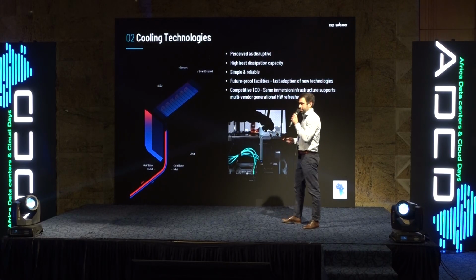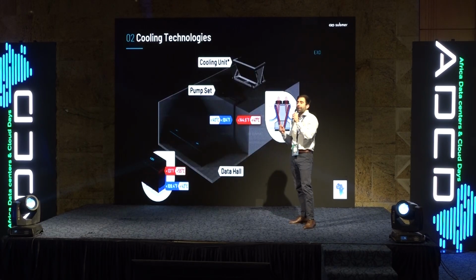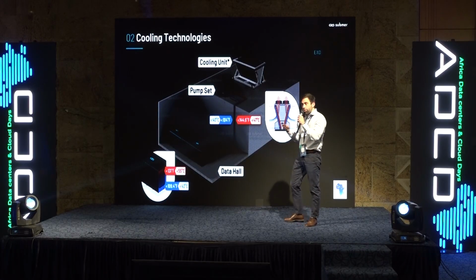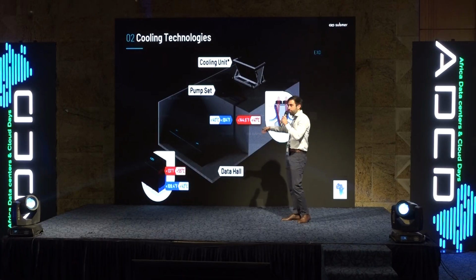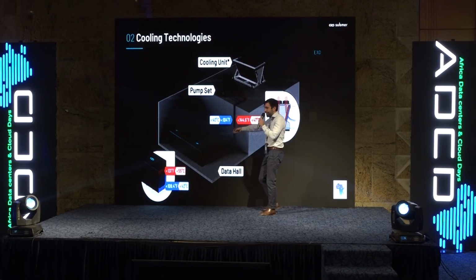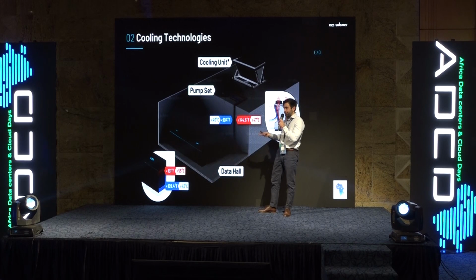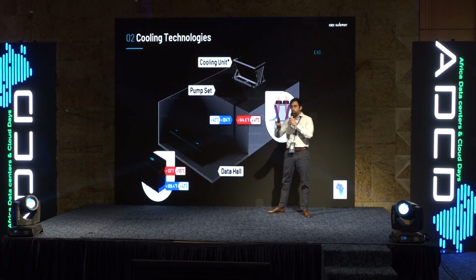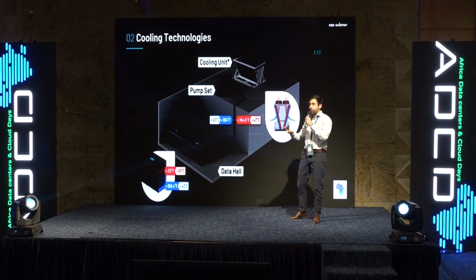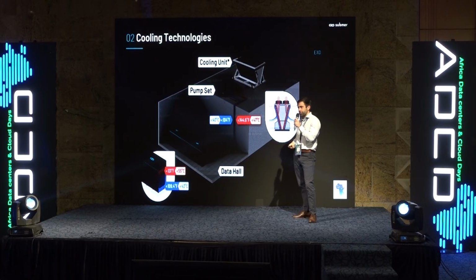So let's start with the second question. The answer is no — you don't need to use cold air for the data hall. If you want it, it's for the comfort of the people operating the data center, but probably 98-99% of the heat generated in the servers stays in the fluid, so you're dissipating the heat from the fluid to the water loop, 100%. In the case of DLC, direct liquid cooling, which is another type of liquid cooling technology, there you need two water loops — one for cold air and another for the DLC solution.